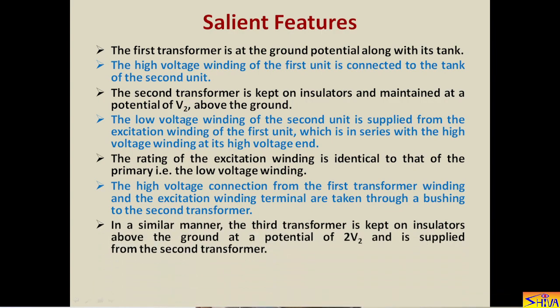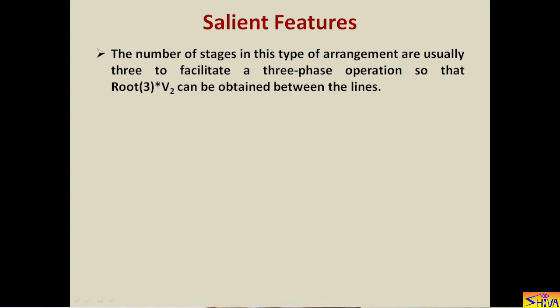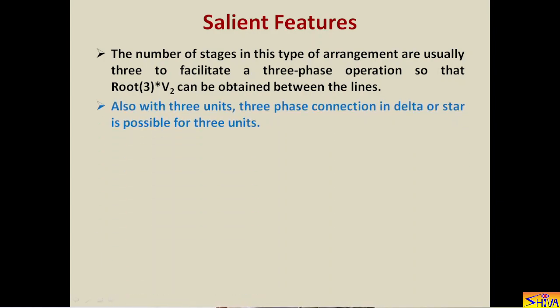In a similar manner, the third transformer is kept on insulators above ground at a potential of twice V2 and is supplied from the second transformer. The number of stages in this type of arrangement is usually three to facilitate three-phase operation, so that √3 × V2 can be obtained between the lines — phase voltage is V2 and line voltage is √3 × V2. With three units, a three-phase connection in delta or star is possible; if units are more than three, this type of connection is not possible. These are the reasons why normally we keep three units.